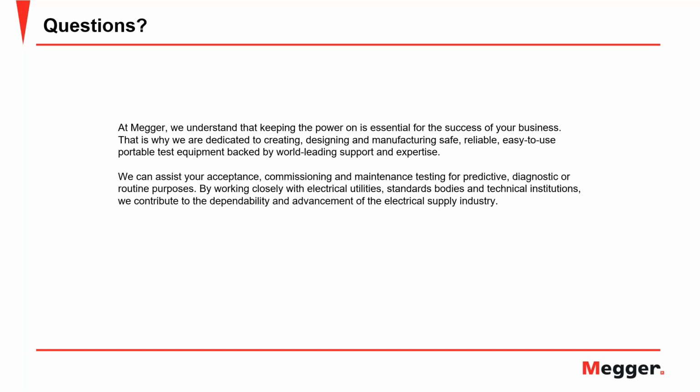So anytime you run into values that have improved, or we have seen cases where you run into negative power factor, and we all know that the best power factor you can hope for is 0, it's an indication that something is not right. That could be a user error, or most of the time what we have seen is that there is a grounding issue, or there is surface leakage happening on the surface of the bushing. That could be because of condensation on the bushing, dirt, or a high humidity environment that can certainly affect the surface leakage current.